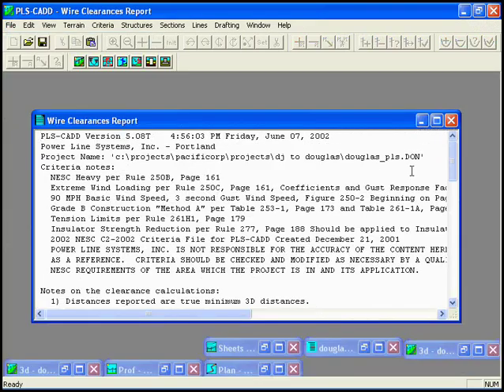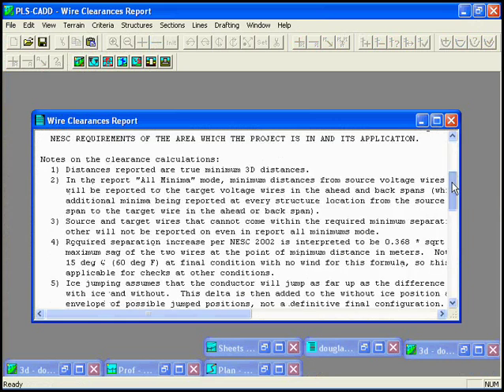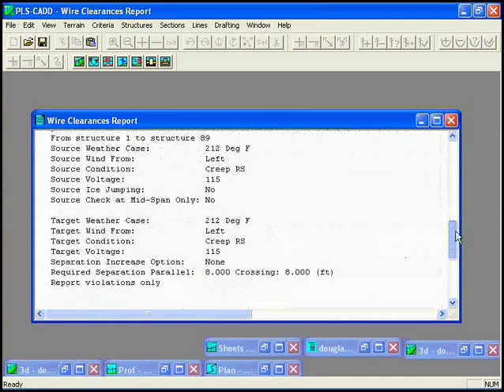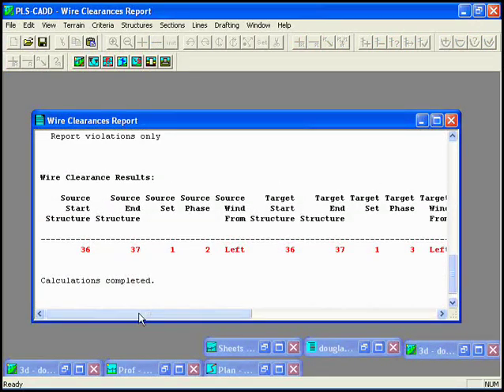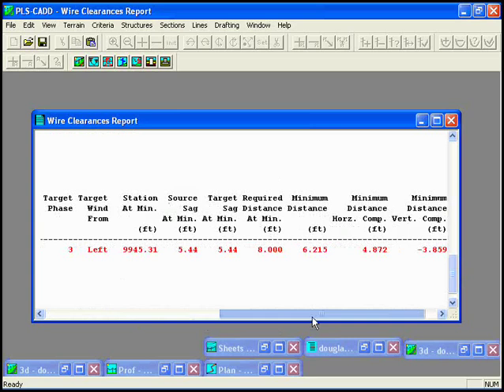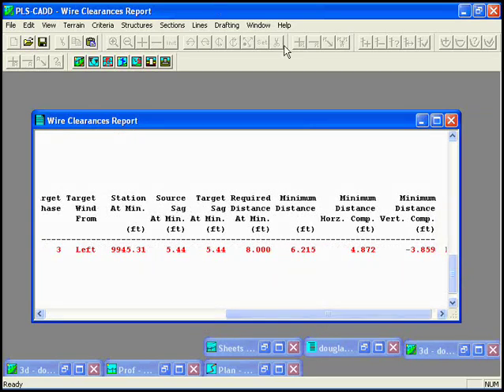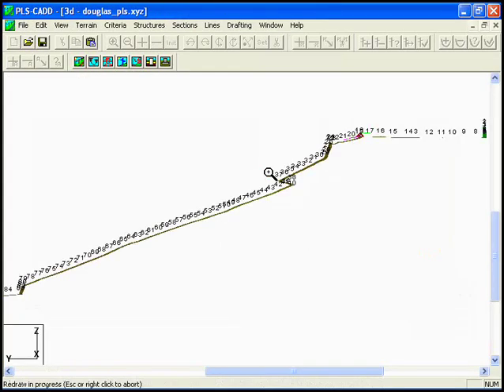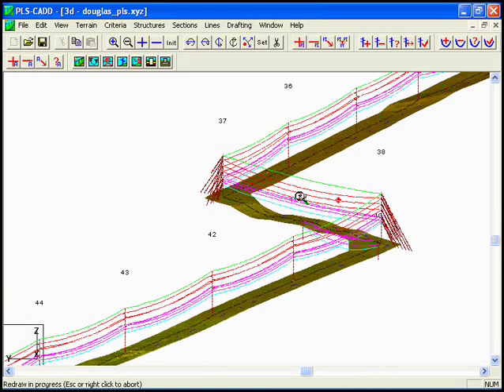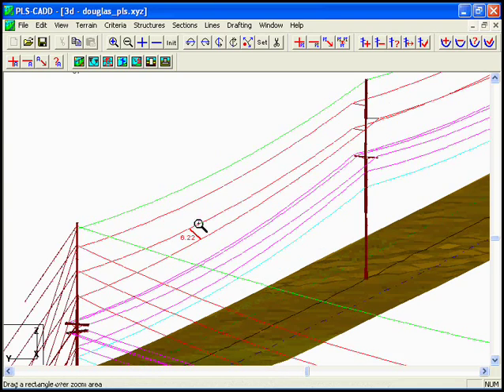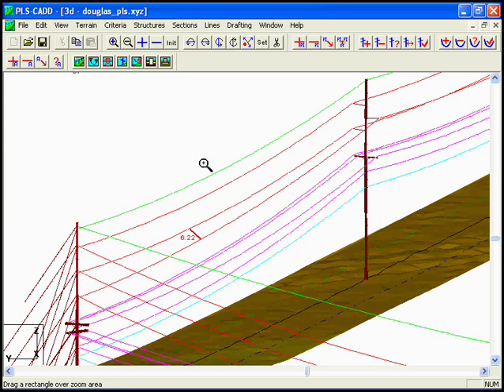We have a report and we can see that we do have one clearance problem between structures 36 and 37. So we'll look at that in 3D view, and we can see a red mark right here in our 3D. We'll start zooming in, and we can see in three dimensions that clearance is between the 115 kV circuits, and we did a unique rolling from the delta configuration into the vertical configuration to illustrate how we can find that minimum clearance.